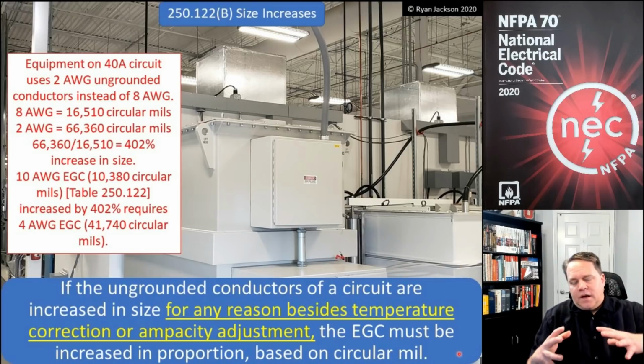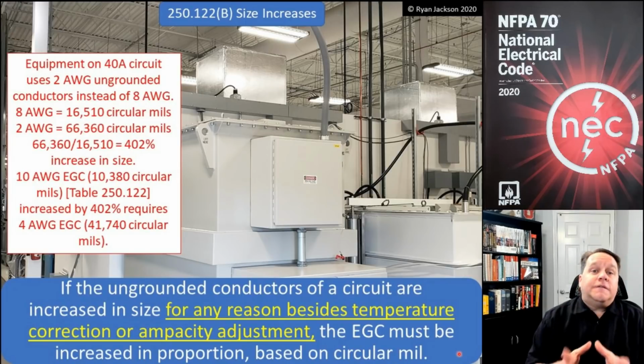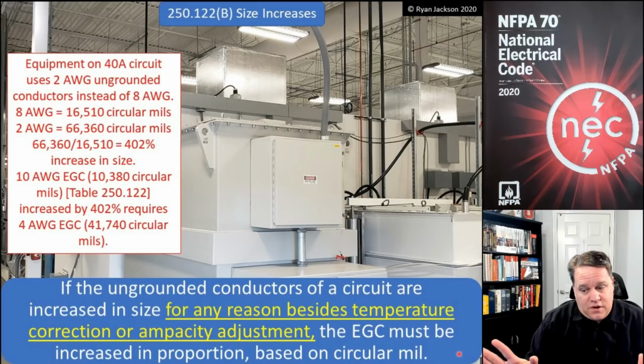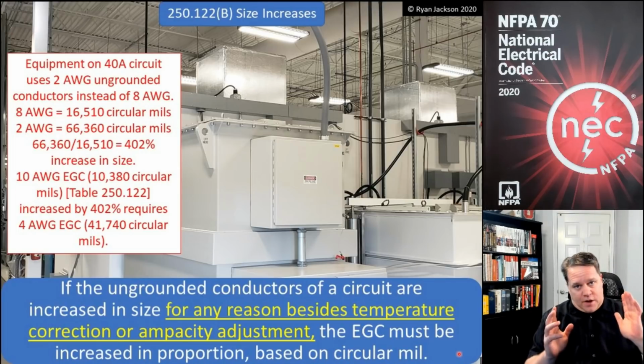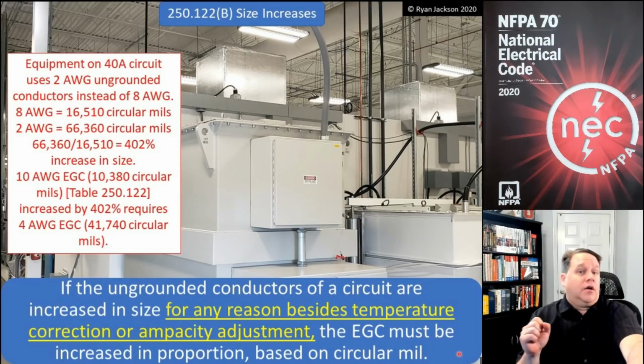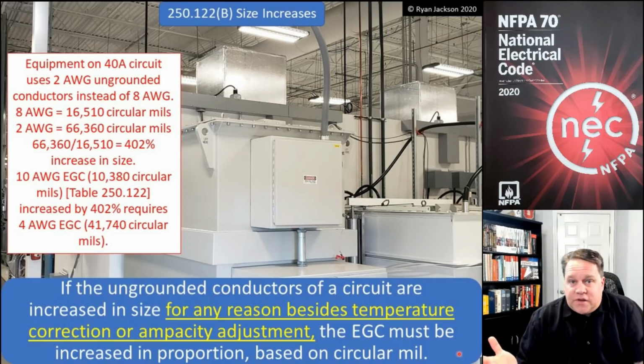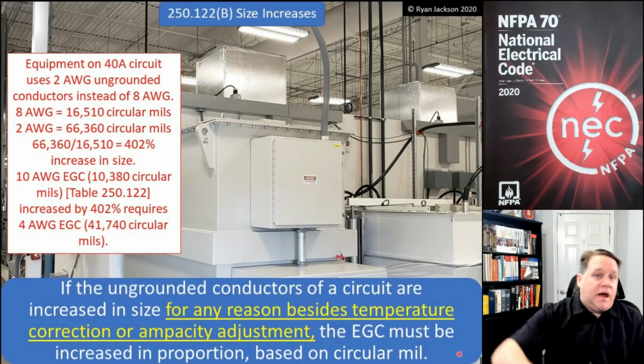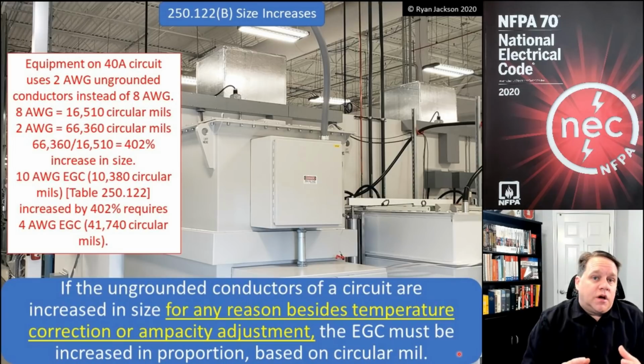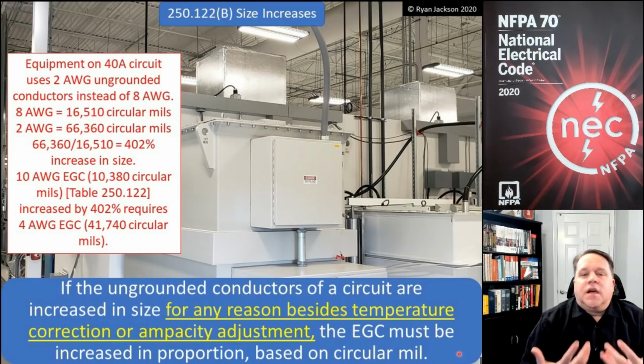Now, here's the problem. If this is for voltage drop, it makes perfect sense. Look, if you have so much voltage drop that you had to make the black wire bigger, you're going to have the same problem on the green wire, and you're going to have to make it bigger. Otherwise, we're not going to be able to generate enough current to initiate the overcurrent device in the event of a ground fault. So it makes perfect sense to increase it for voltage drop. But sometimes it doesn't make any sense at all.